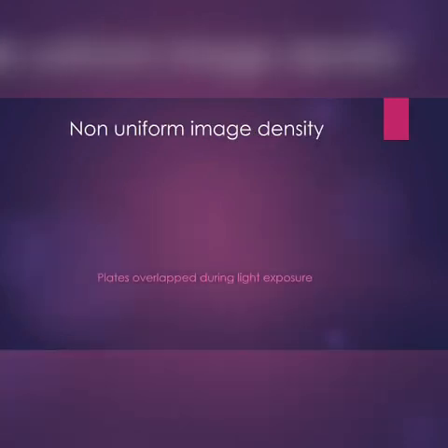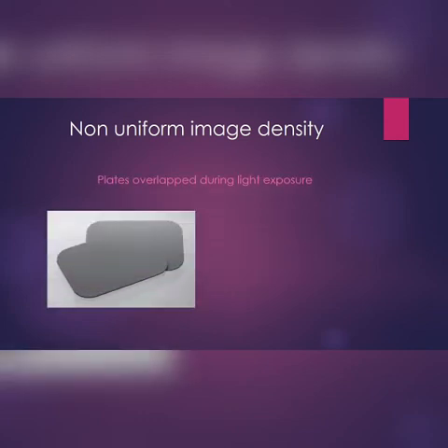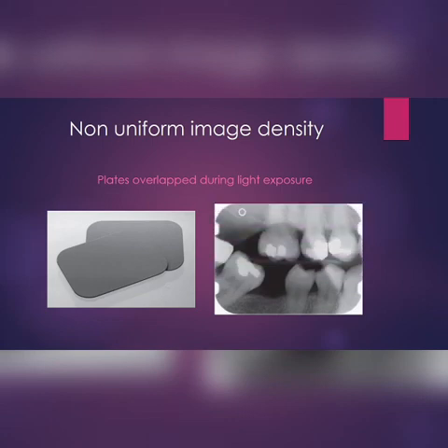Alright, a non-uniform image density. This is very common when the plates are overlapped during the light exposure. You can see that the image density is slightly compromised, so the image quality is also getting affected here, and a degraded image is produced.